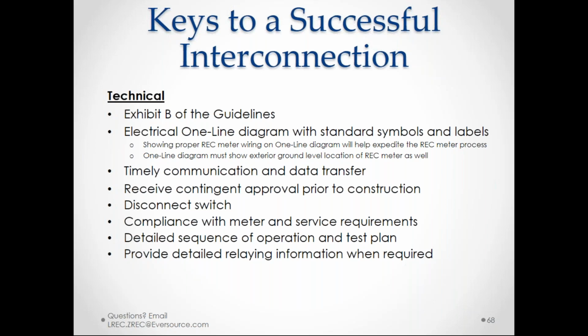Again, if you want this interconnection to be successful, timely communication of the right data. You're going to receive a contingent approval prior to construction. The disconnect switch is still a requirement. Please make sure that the AC disconnect switch is in an exterior ground level location. There are a few exceptions to that requirement, and you have to request that. Please don't assume, but the limited cases in which we will potentially allow an interior disconnect are municipal facilities, such as schools, where we know that tampering with the switch could be a concern.